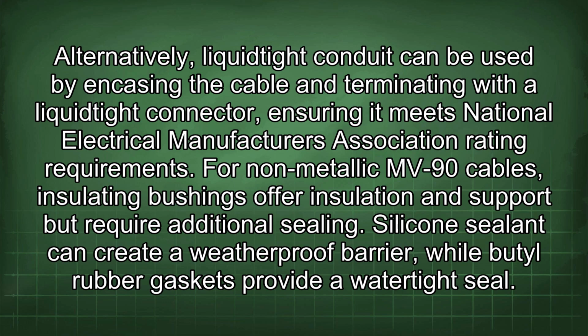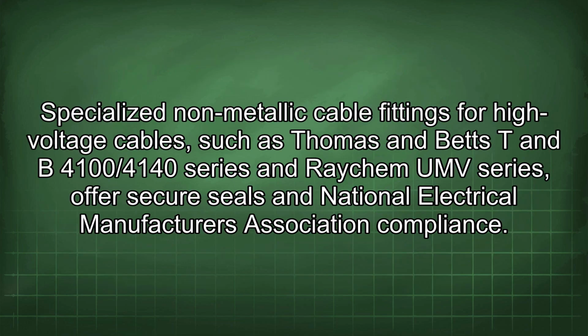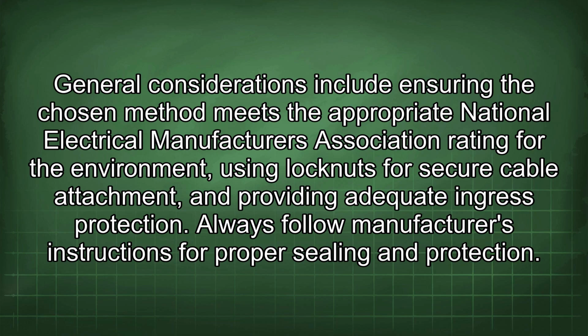For non-metallic MV-90 cables, insulating bushings offer insulation and support but require additional sealing. Silicone sealant can create a weatherproof barrier, while butyl rubber gaskets provide a watertight seal. Specialized non-metallic cable fittings for high-voltage cables, such as Thomas and Betts T and B 4100/4140 series and Raychem UMV series, offer secure seals and National Electrical Manufacturers Association compliance. General considerations include ensuring the chosen method meets the appropriate National Electrical Manufacturers Association rating for the environment, using lock nuts for secure cable attachment, and providing adequate ingress protection. Always follow manufacturer's instructions for proper sealing and protection.